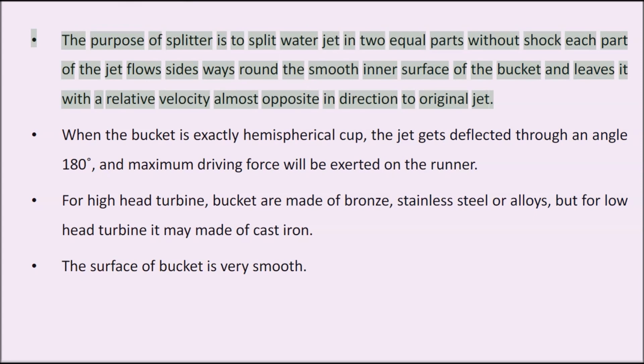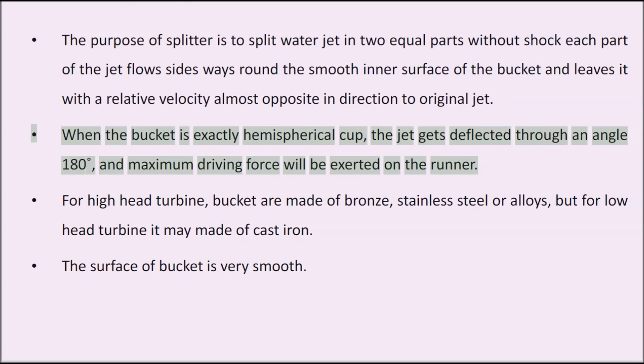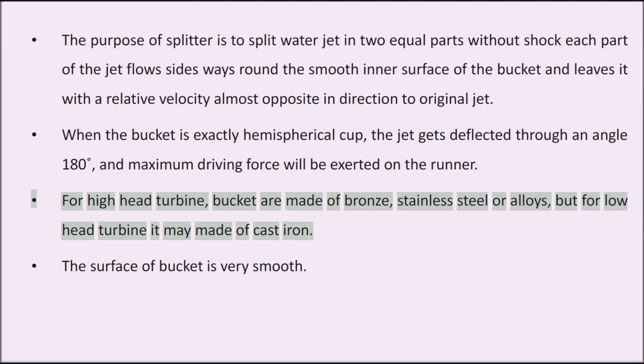When the bucket is exactly hemispherical, the jet gets deflected through an angle of 180 degrees and maximum driving force is exerted on the runner. For high-head turbines, buckets are made of bronze, stainless steel, or alloys, but for low-head turbines they may be made of cast iron. The surface of the bucket is very smooth.